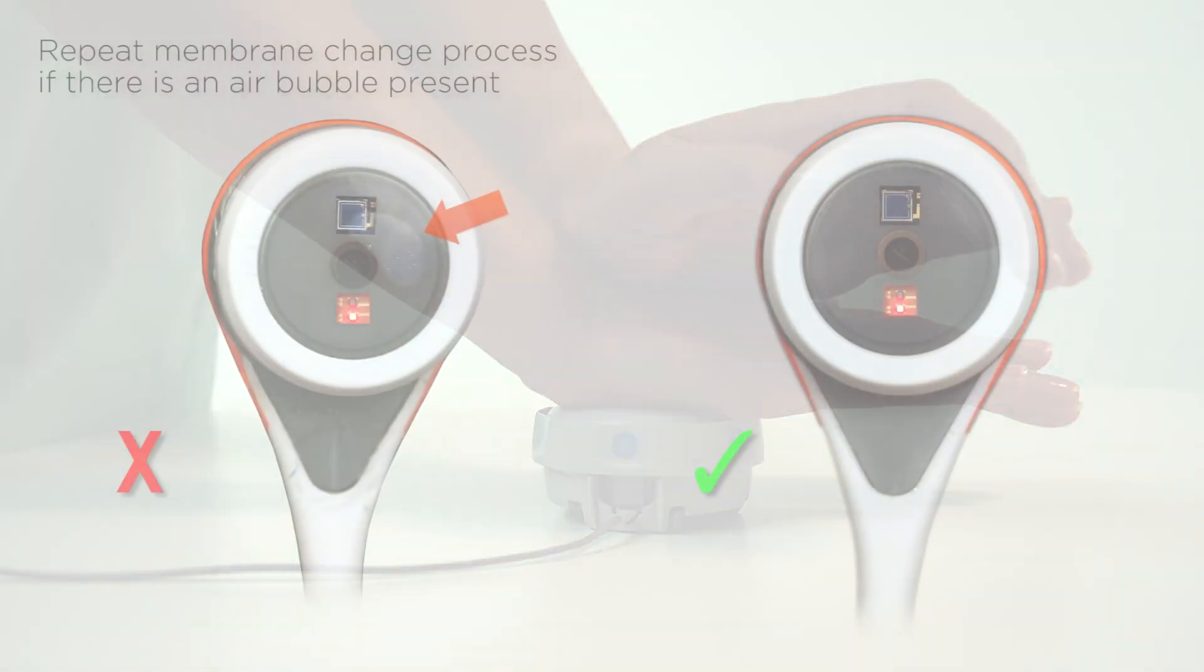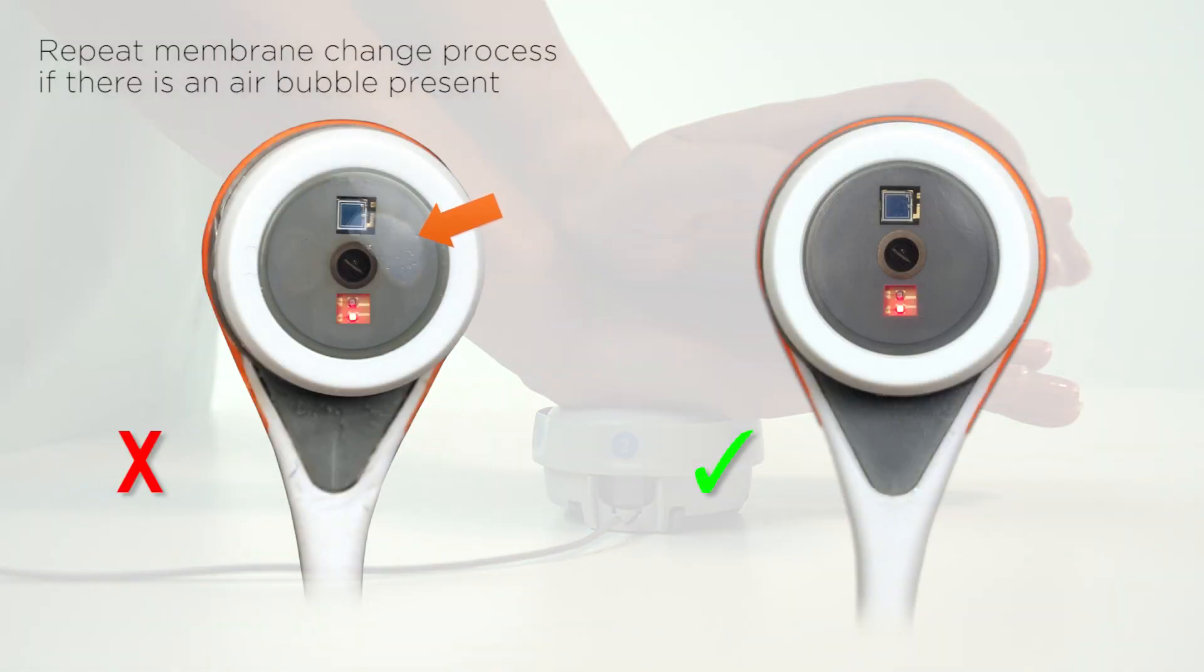Make sure that there are no air bubbles and verify that the membrane is correctly seated on the sensor.